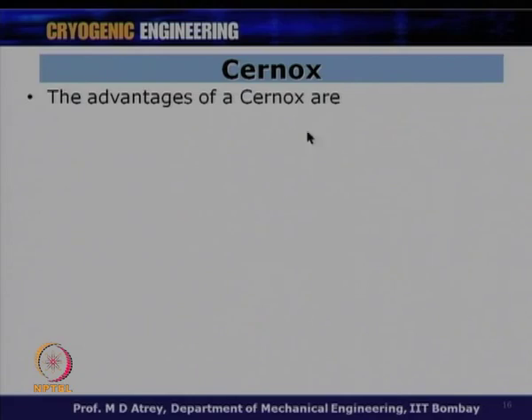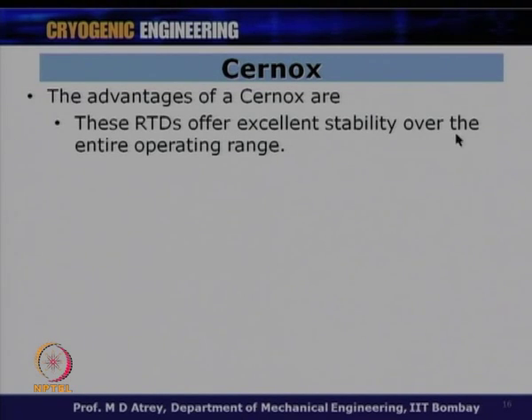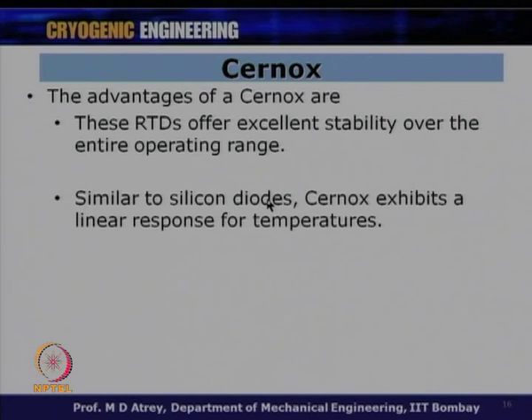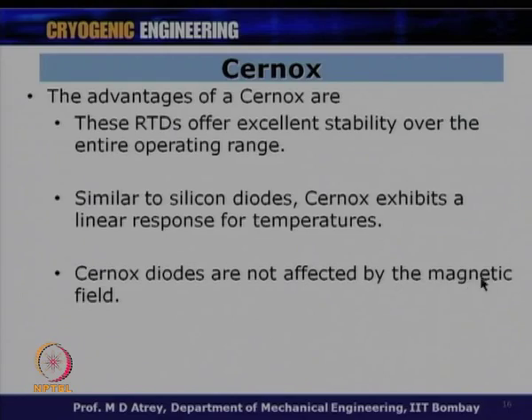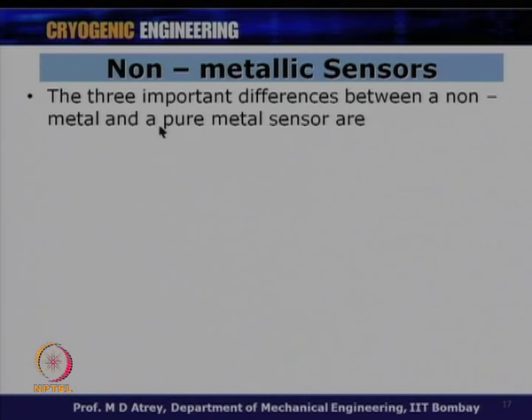The advantages of Cernox are that these RTDs offer excellent stability over the entire operating range. Similar to silicon diodes, Cernox exhibits a linear response for temperatures. Importantly, Cernox sensors are not significantly affected by magnetic fields — which is one of their biggest advantages. This is a key difference from silicon diodes.